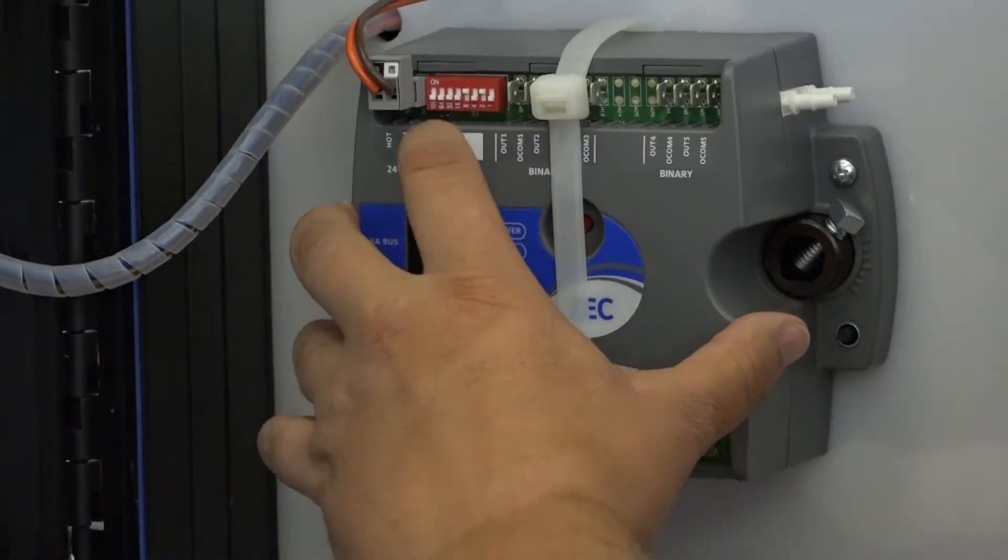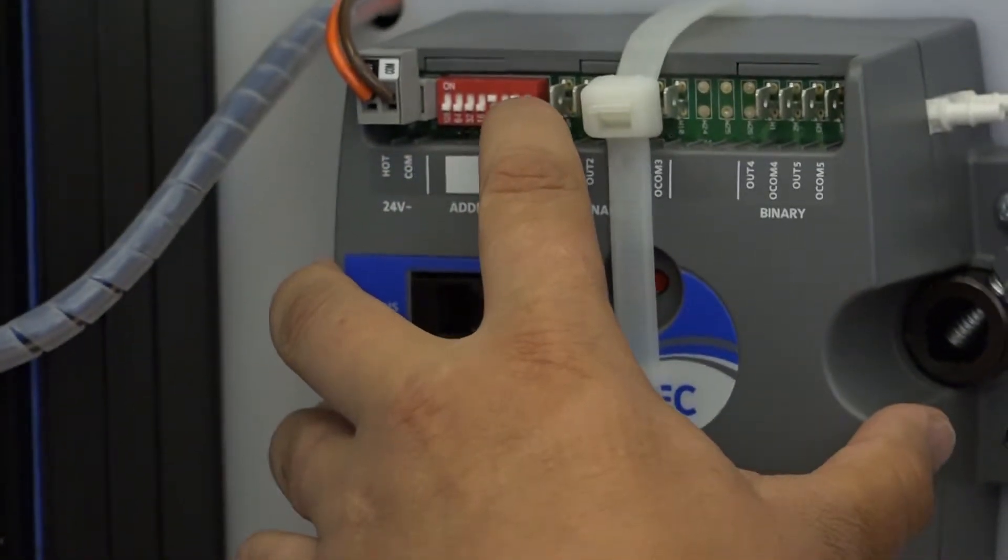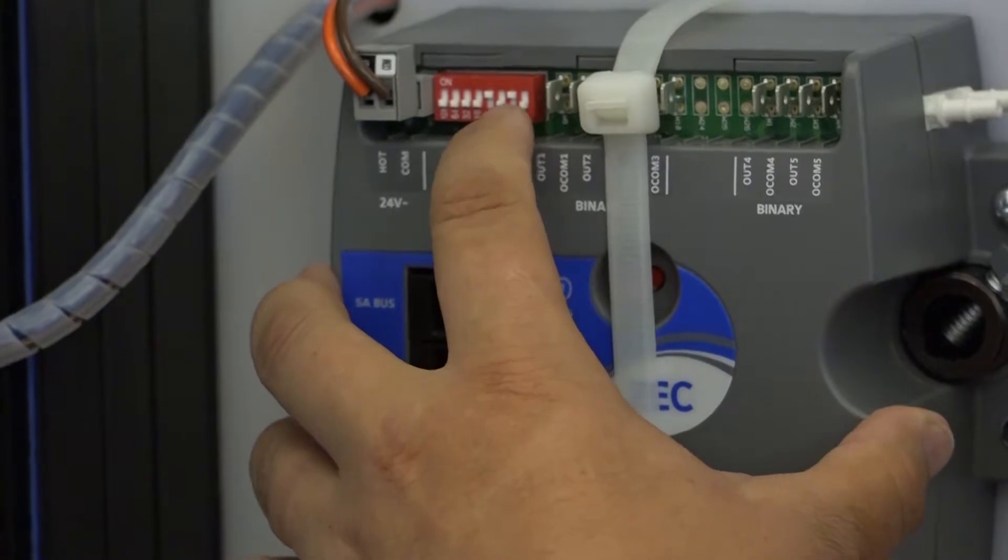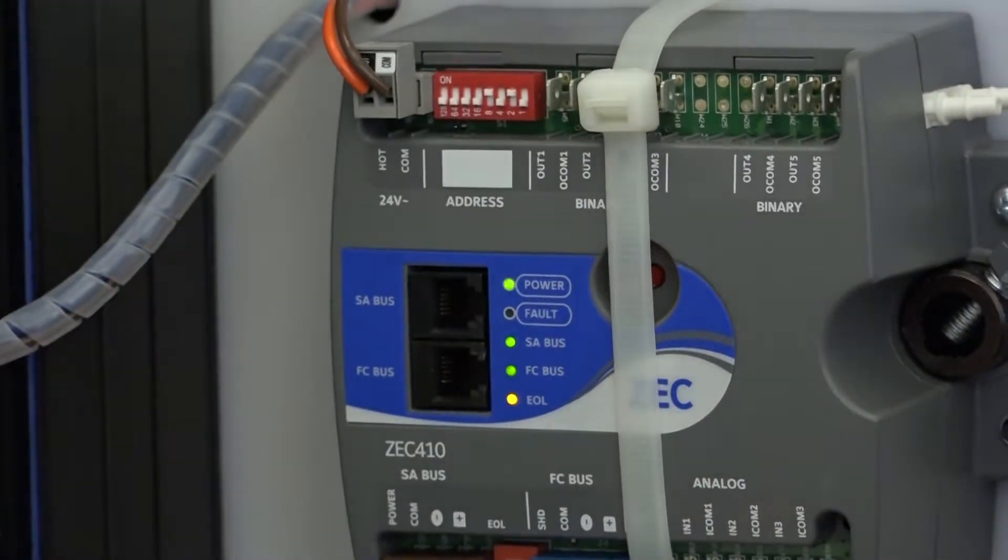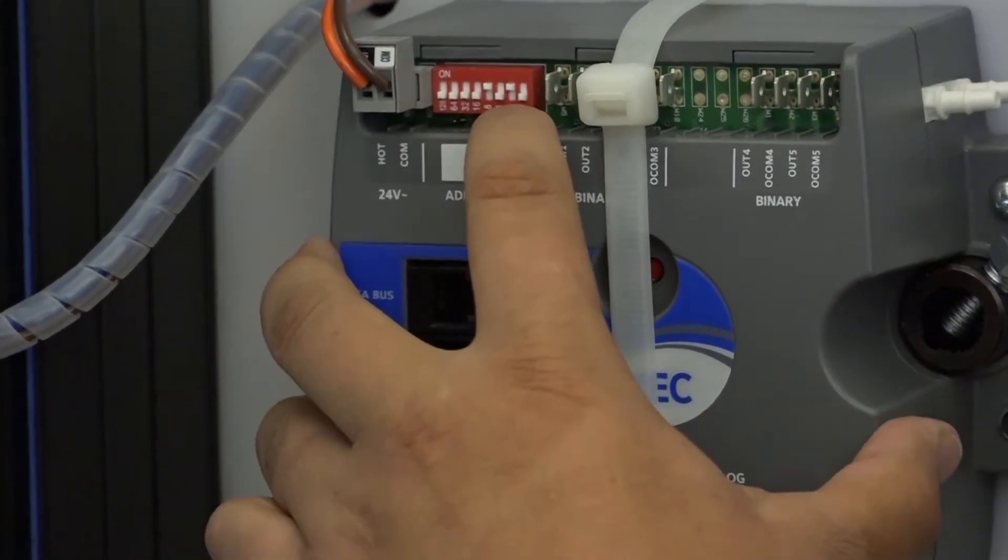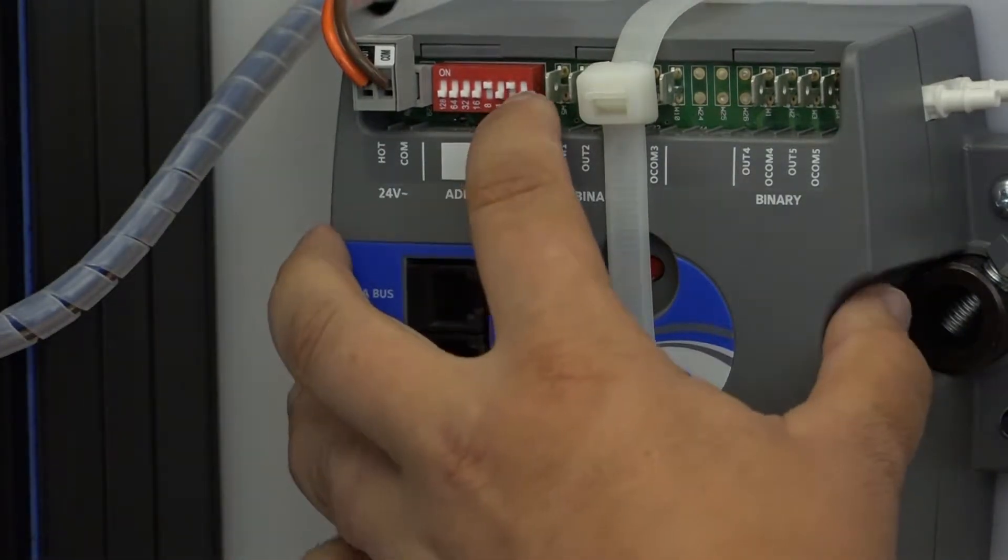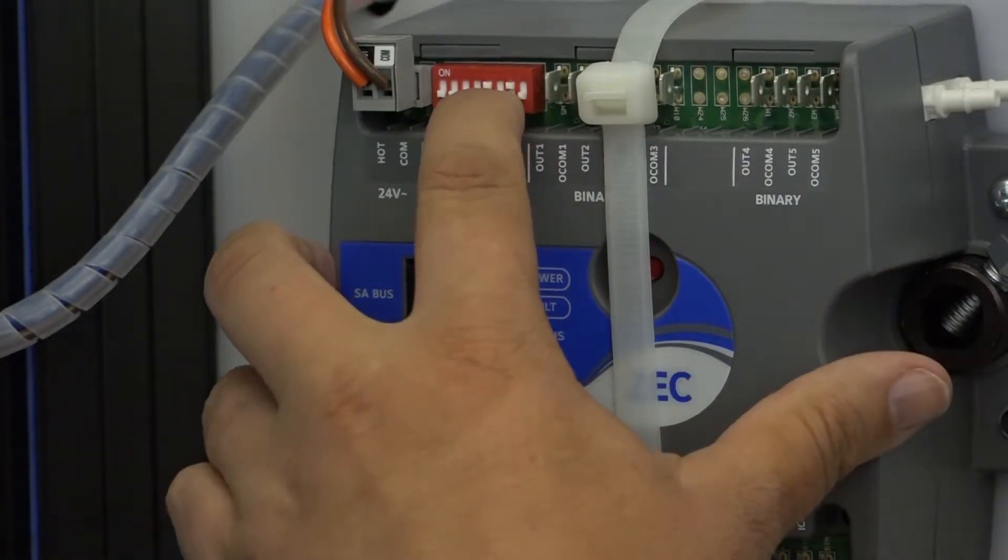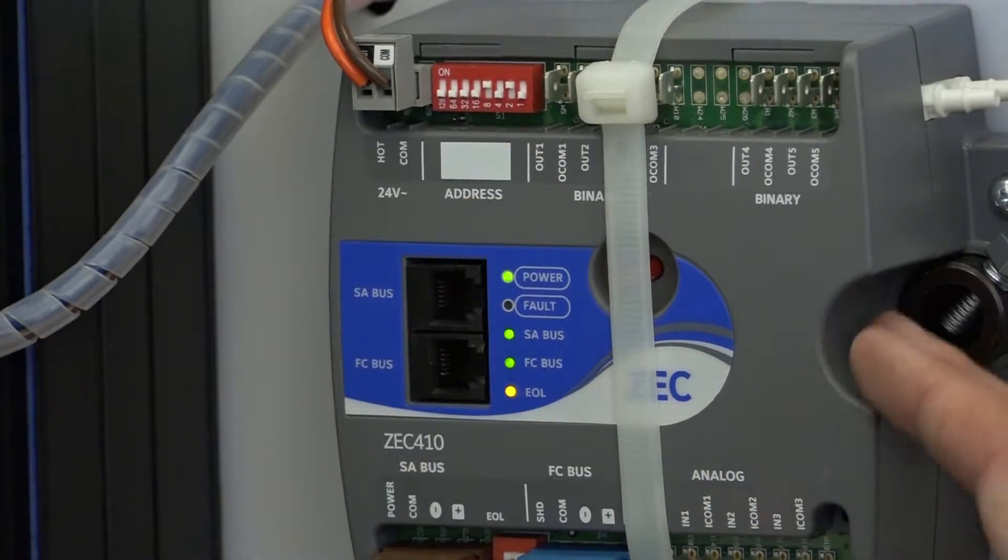The address switch is a binary switch. So you'll see a 1, a 2, a 4, an 8, a 16, and so on. To set the address, you turn on the switches to add up to the address you want. So in this case I have switch number 2 and switch number 8 are on. That means that the address of this controller is 10.